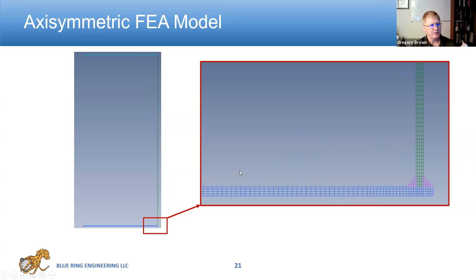But since we're worried about settlement, how do we actually model tank settlement? Well, we take that model and we put it on the soil, on the foundation. We give the soil the shape that was measured, and then we put the load on the tank, allow the tank to settle into the floor. What this causes is the bending you see in the tank floor and the shell. We can use that to determine if it's acceptable.